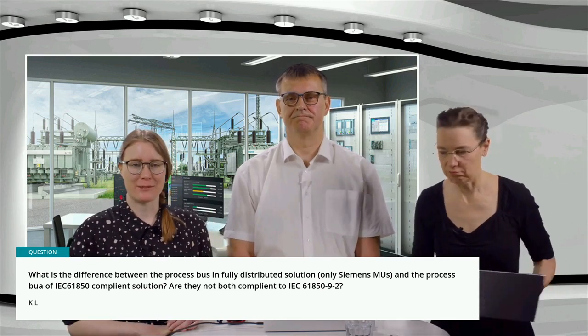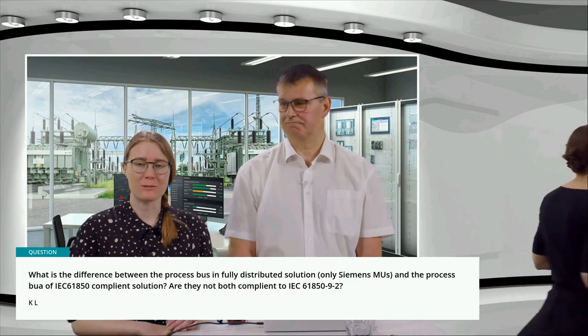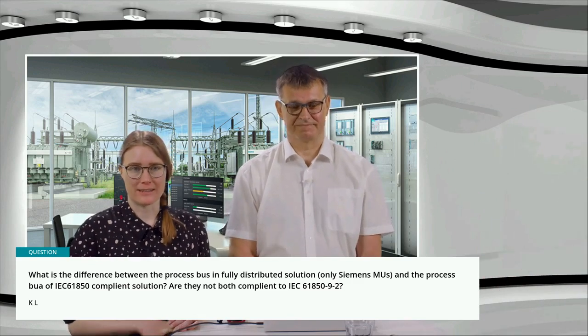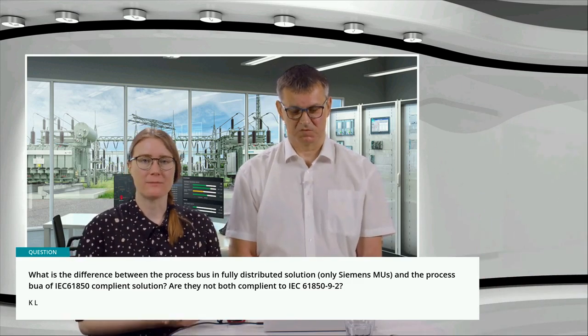The difference is that for the 7SS85CU solution, there's a simplified engineering process, and the stream time is fixed to 4000 Hertz, 1 ASDU. And for the binary signals, there are some extensions.